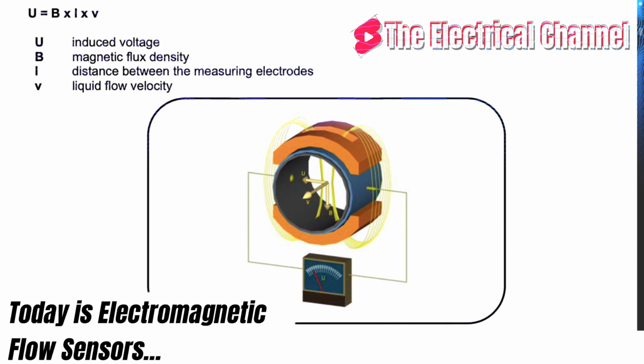Now, if a conductive liquid flows across magnetic field B, voltage U will appear on the measuring electrodes proportional to the flow velocity v and the conductor length l. Therefore, U equals B times l times v. As the magnetic flux density and distance between the electrodes are constant, the induced voltage is proportional to the liquid flow velocity in the tube.